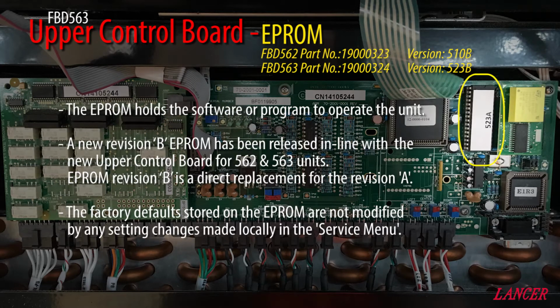The EEPROM is a pre-programmed chip that holds the program or software to manage the FBD unit. The EEPROM has factory-loaded defaults or settings that will enable a consistently good product without any modification by a technician. Any changes or tweaks made to this program via the service menu will not overwrite the EEPROM software. These changes are held by onboard memory chips. As of November 2015, new FBD units, both the 562 and 563, have a B variant EEPROM in line with the new upper control board released at the same time.